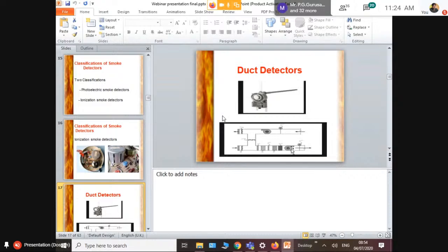Similarly, you will have another. This is a supply duct, if you can see the direction. And if you come here, it's all the way the other way around. It's a return duct, so from here it is going outside. You see the fan directions. This is how it is. So when the smoke detector is installed on this side, if there is a fire either inside this area or from somewhere supplied here, you will have a smoke detection indicated, and this will give information to the main control panel again.